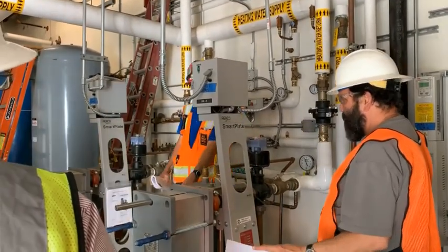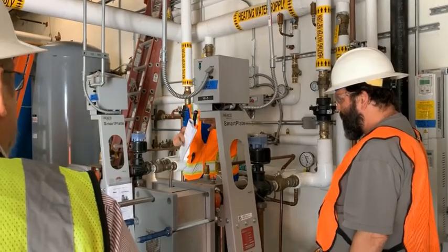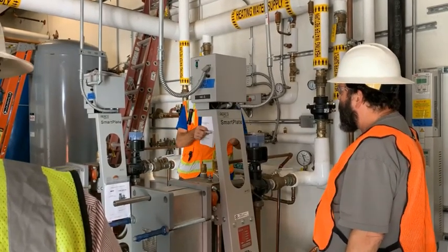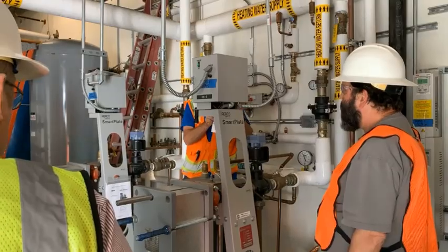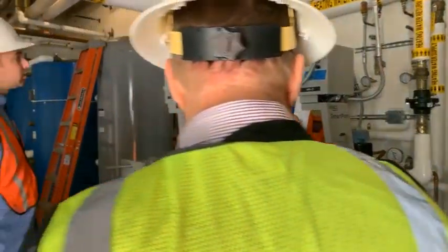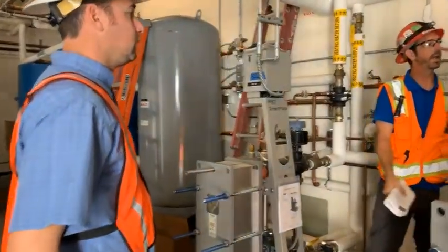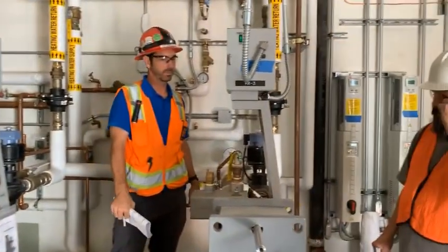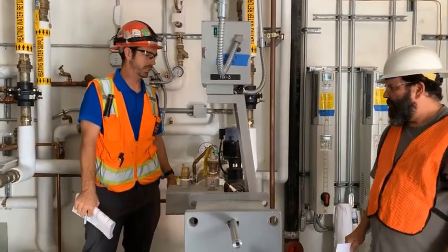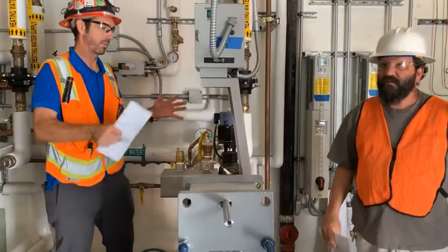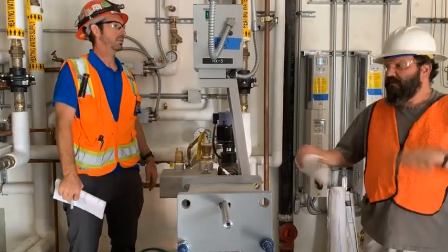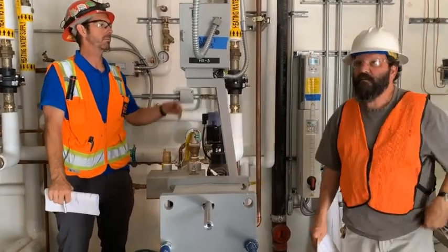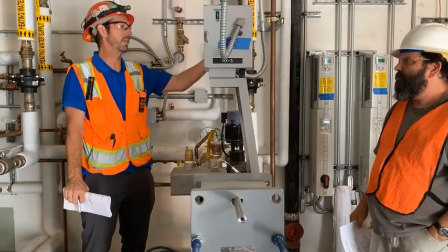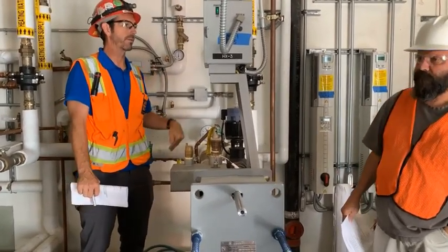But there's drip holes in the heat exchangers. So if you ever saw water dripping out of the heat exchangers, it's probably because there's dual elements, so the waters can't touch. And if it does leak out of one, you'll see a leak out the bottom. We'll get over that tomorrow with the heat exchanger training. So if the heating water's down, then you have no domestic hot water. Yeah, the entire heating hot water system is down, right? You wouldn't have domestic hot water.